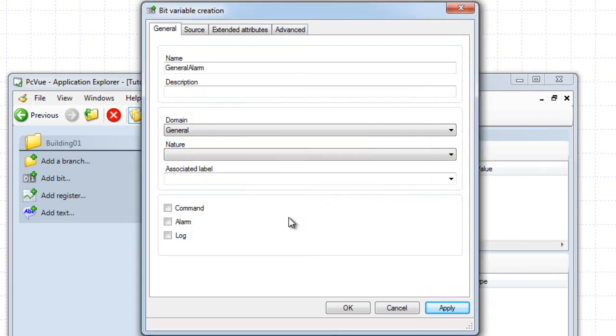To configure the bit as an alarm, just tick the Alarm property, and to be able to simulate the value, set the Command property. Once configured as an alarm, the behavior of the variable is modified so that the real-time value visible to the user has five possible states instead of three for a bit, depending not only on the value of the underlying bit variable, but also on the action of the user. The best way to understand the various alarm statuses is to examine the alarm life cycle.